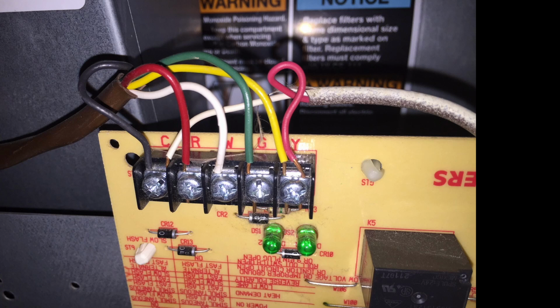The LED bulbs or LED indicators that I was talking about, these are green. If you see them, they're right below there. And these will signal back and forth if there's a problem within the system. Most of your control boards are either White Rodgers or other types of company. A lot of them use White Rodgers nowadays. And that's what you look at. It's a simple setup, but this is how you would wire it in. So after you wired your thermostat up, this is where you would go to your control board. You would see the same markings as you would on your thermostat, except make sure that the other wire that's outdoor goes into cool and common.